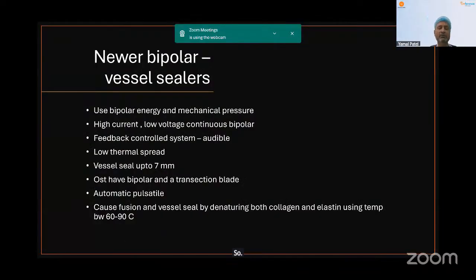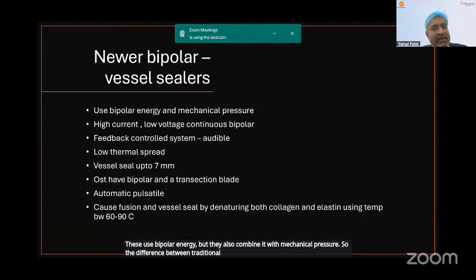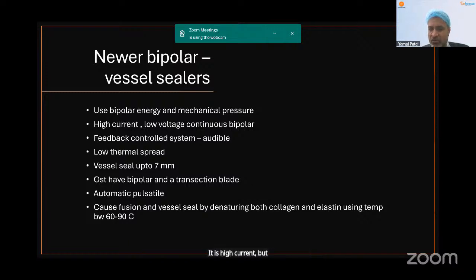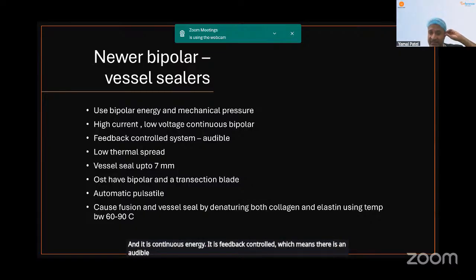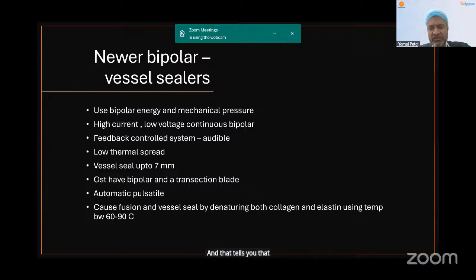So newer bipolars, also called vessel sealers, were created. These use bipolar energy, but they also combine it with mechanical pressure. So the difference between traditional bipolar and newer bipolar is that the newer bipolar works with bipolar energy and mechanical pressure. It is high current but low voltage. Low voltage means low risk, and it is continuous energy. It is feedback controlled, which means there is an audible sound that tells you the tissue is ready. When you press it, after a while it will give you an alert, toot, toot, toot, and that tells you that the tissue is adequately coagulated. That's safe to now cut.